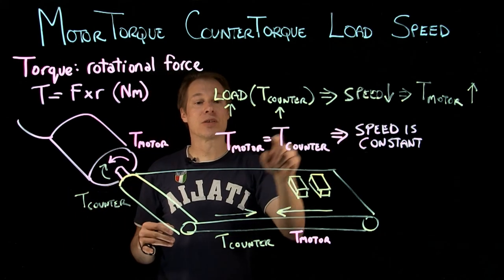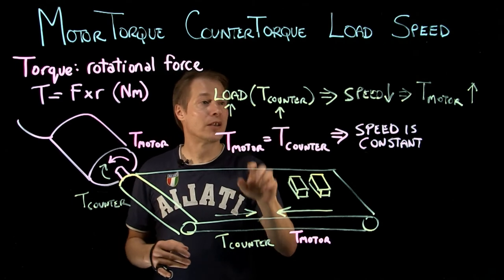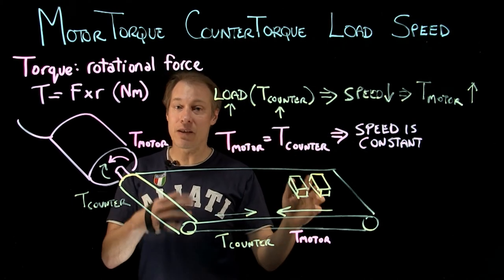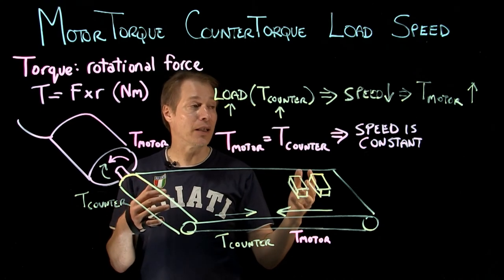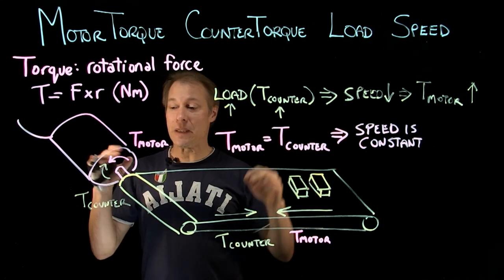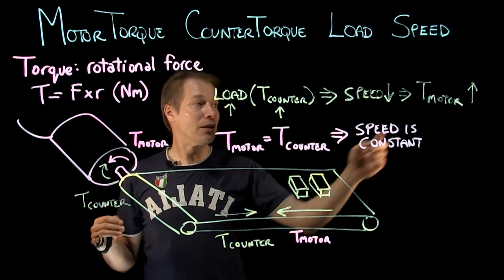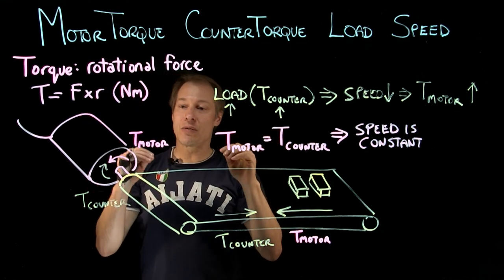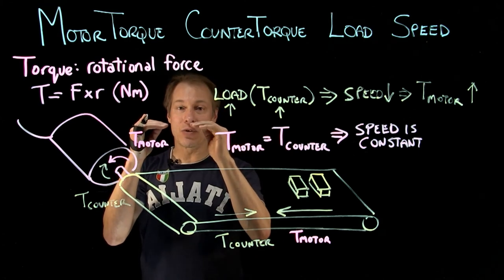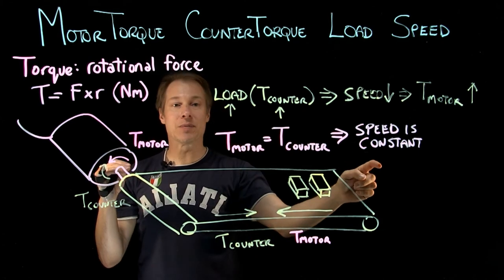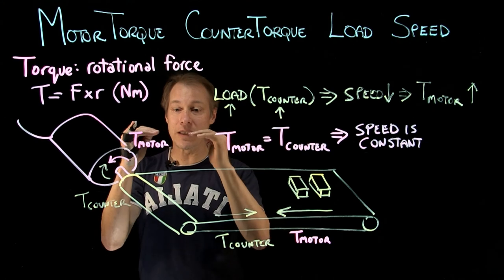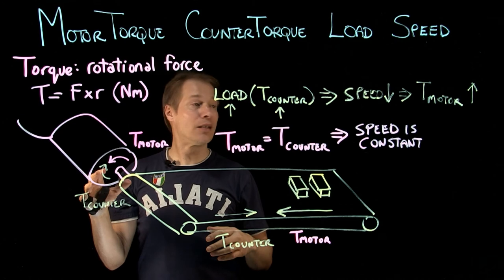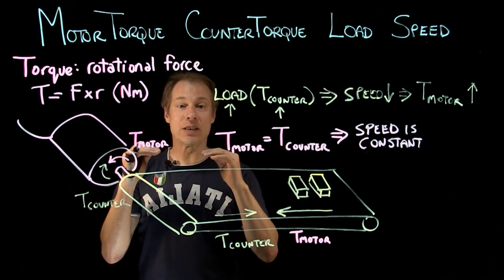Let's start over again. As load goes up, counter torque goes up, because they're the same thing. Then the speed of the motor slows down. When the speed slows down, the torque of the motor goes up. As the motor torque rises to match the counter torque, when they are even, the speed will stabilize — it will be a new constant speed, lower than it was before, but it will remain constant.